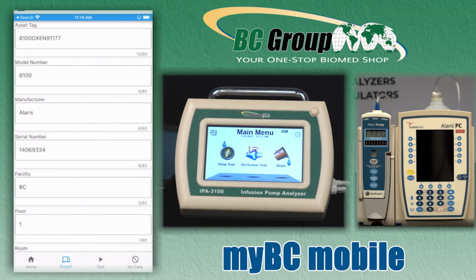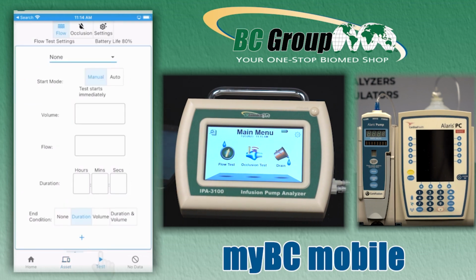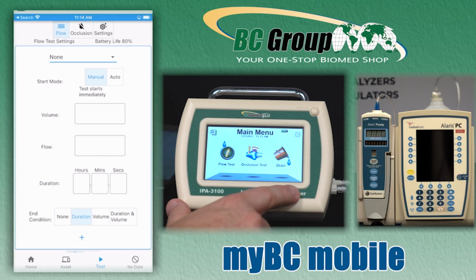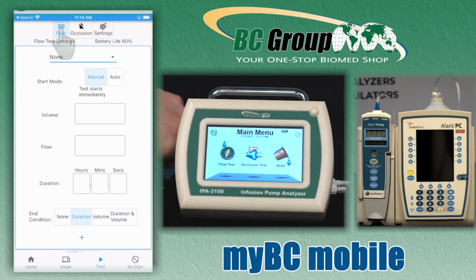And then it's going to confirm the asset information. So do you have the right asset selected? We can double check our equipment and make sure we've got the right serial number selected. Yes, that's the one. And then we can run our testing. At this point, I have the same selections at the top that I do from the main screen. So I can either do flow testing or occlusion testing or adjust my settings. And we're going to do a flow test.